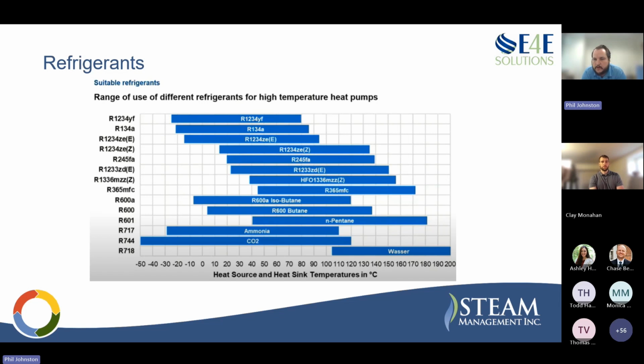And there are regulation aspects to this as well. So refrigerants are getting phased out, and maybe a refrigerant you used for a system before may in the future not be used anymore from an environmental policy standpoint. So it's important to understand that and try to use refrigerants that are future proof, or just be understanding of what you're getting into when that refrigerant is selected.